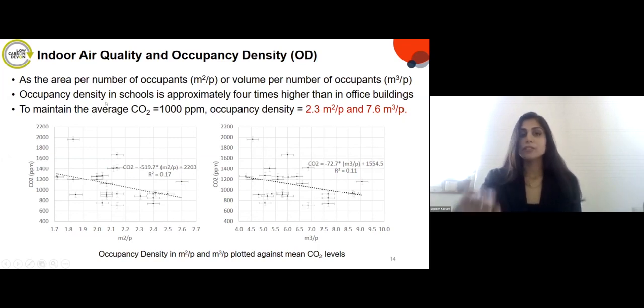Occupancy density — defined as area or volume per number of occupants — is much higher in classrooms than in office buildings because students sit very close together. To maintain a CO2 level of 1,000 ppm, the maximum acceptable for indoor air quality, a minimum occupancy density of 2.3 m² per person and 7.6 m³ per person is needed. These numbers give important recommendations for area, volume and ceiling height in school design.